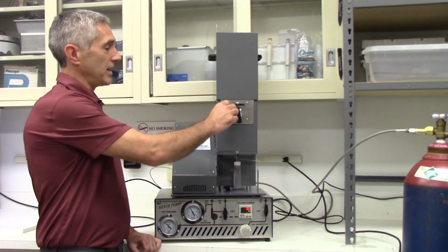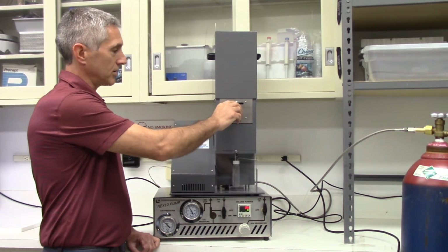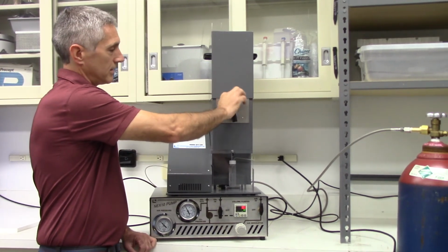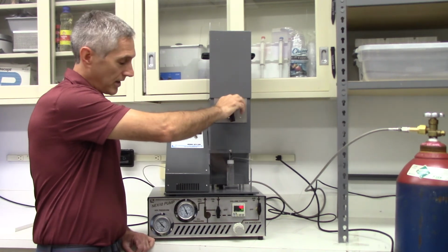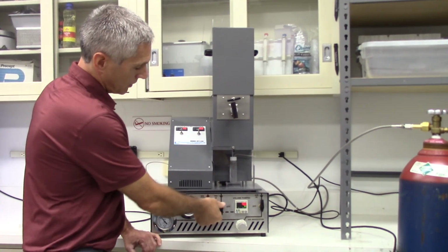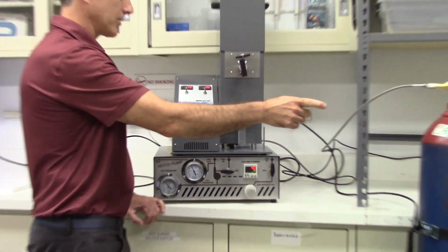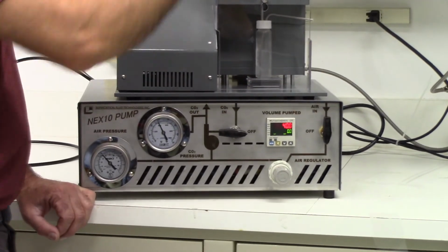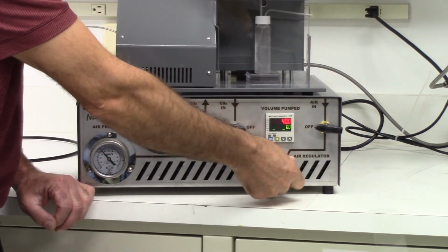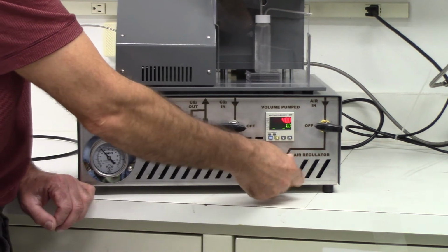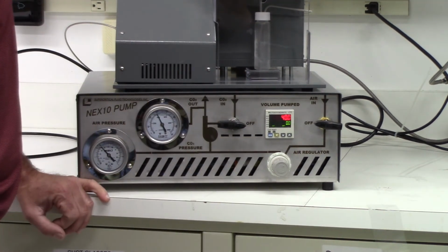When you're ready to vent, your experiment's all done, you want to stop the system, vent it, collect your sample. So we'll shut the static dynamic valve, we'll close the CO2 valve, so this prevents CO2 from coming from the bottle to the extractor through the pump. We'll shut off the air.